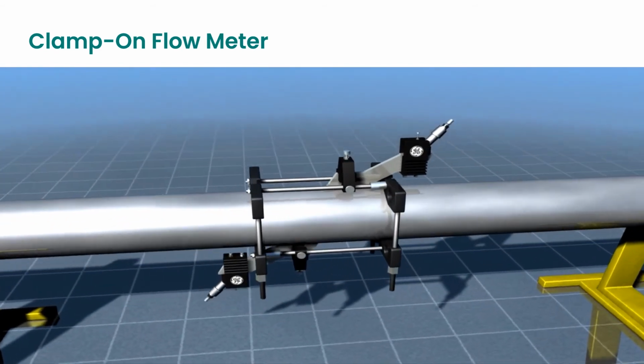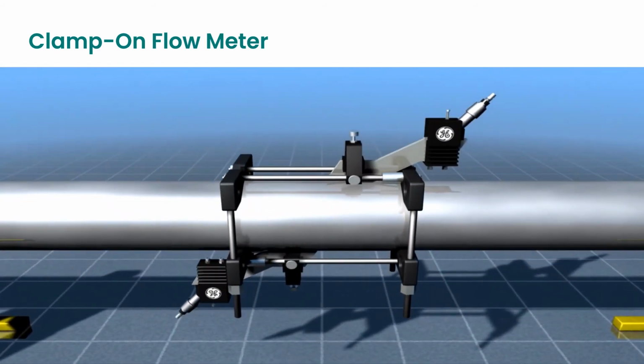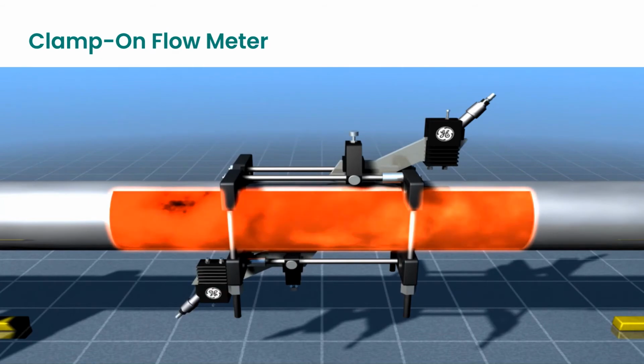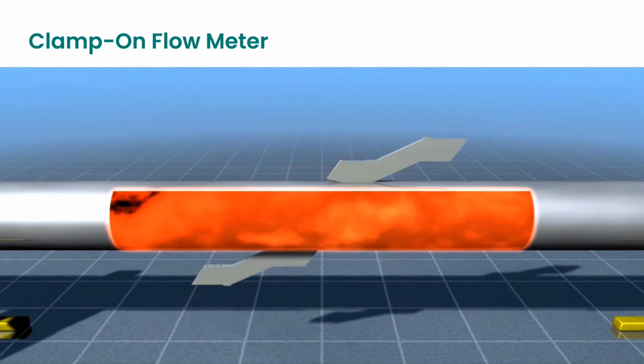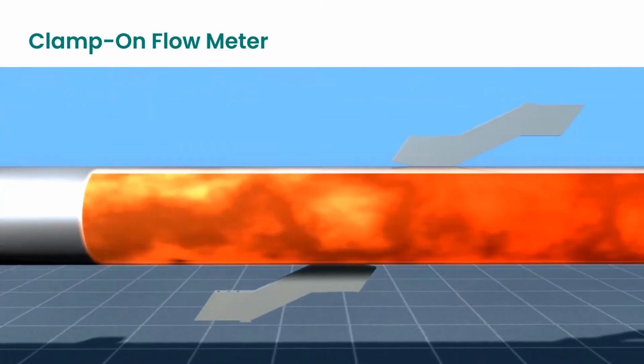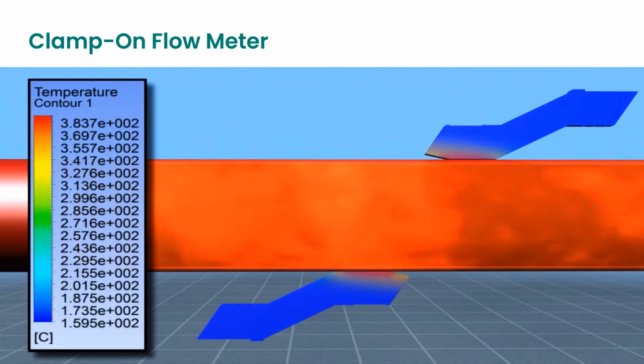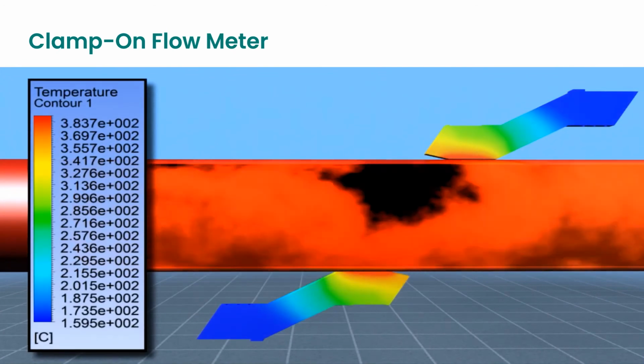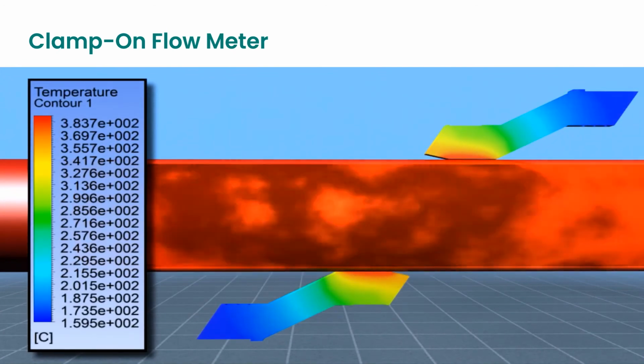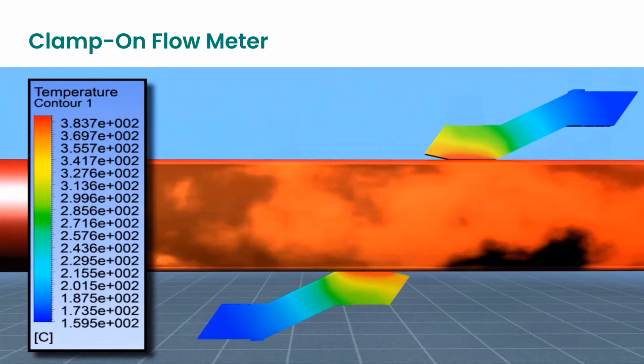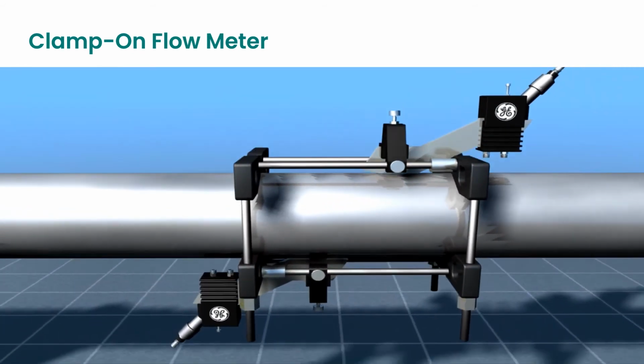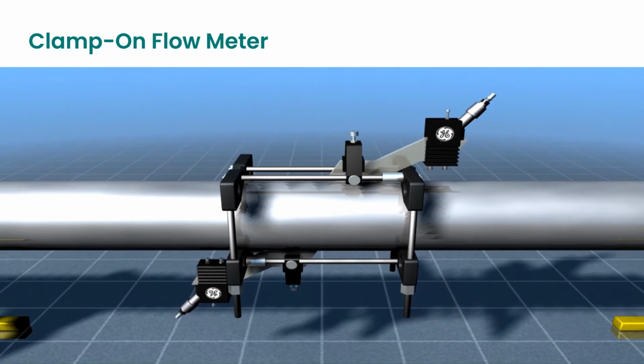Besides the PanaFlow HT, we also have our CET clamp-on transducers for extreme temperature operation. This video illustrates the high temperature of the application and how the CET transducers operate. With the CET waveguide, the transducers are kept at an ambient temperature, isolating them from the process. Our CET transducers have been used to validate flow measurements in multiple locations in which either no flow measurement existed or in which the current flow measurement required scrutiny.